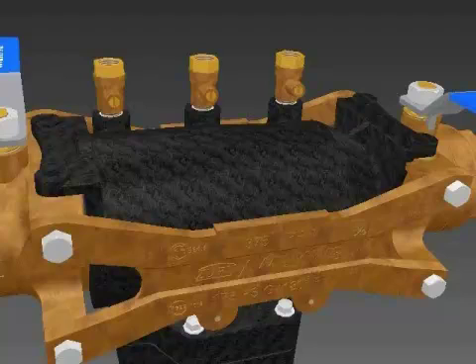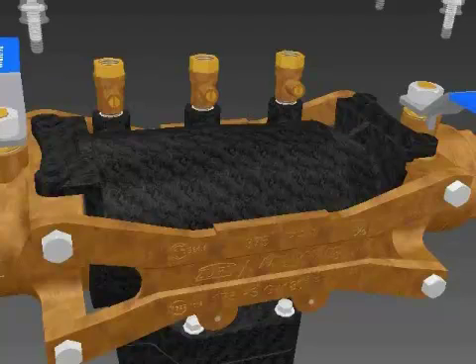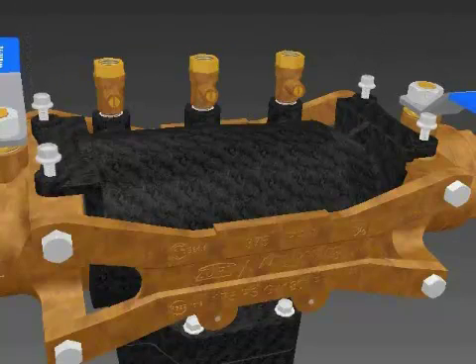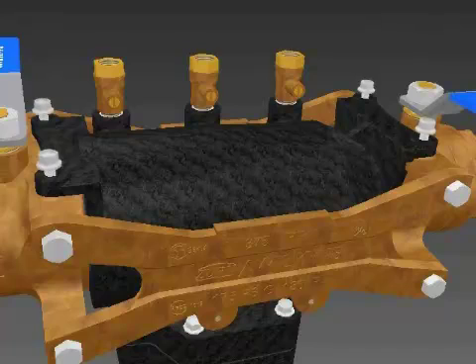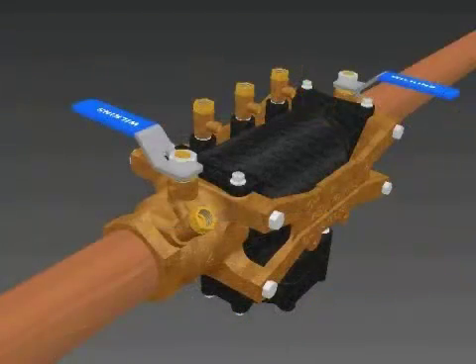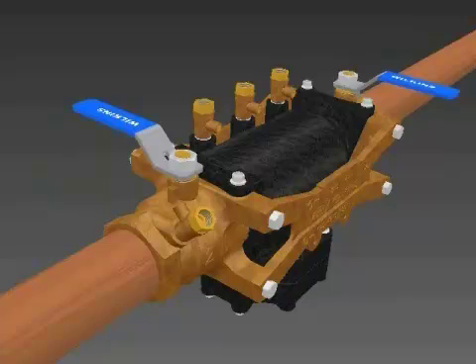After the housing is seated properly, insert the four bolts. Do not over tighten these bolts. Before servicing the relief valve, make sure to check the troubleshooting section of the instructions. The most common cause of discharge from the relief valve is debris in the number one check valve.